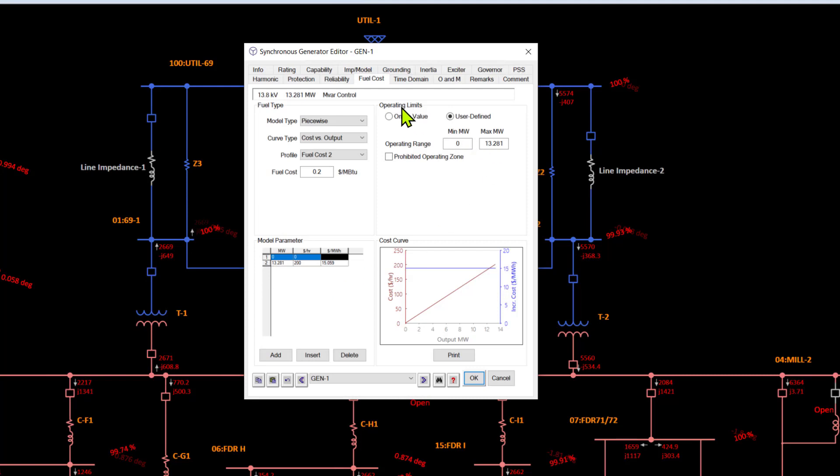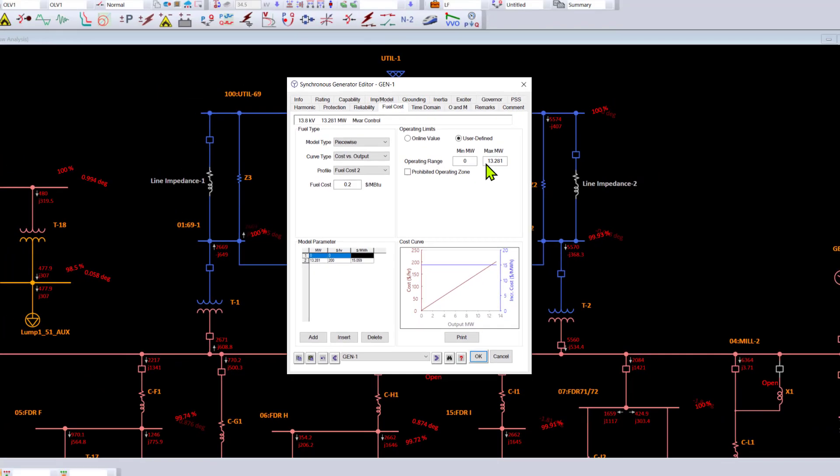You can also define the operating limits which may be beyond the values that are based on the nameplate of the machine. If your generator is 13.28 megawatt, you can define an operating range that is slightly tighter, including certain prohibited operating ranges.